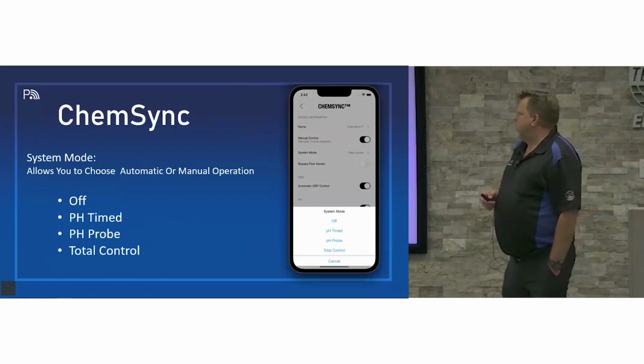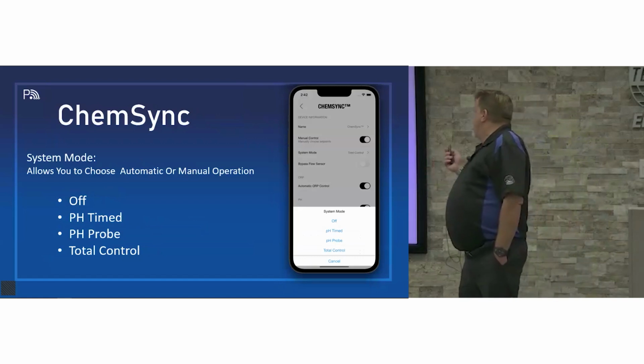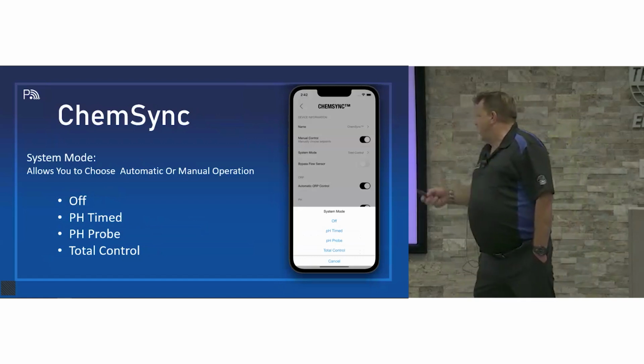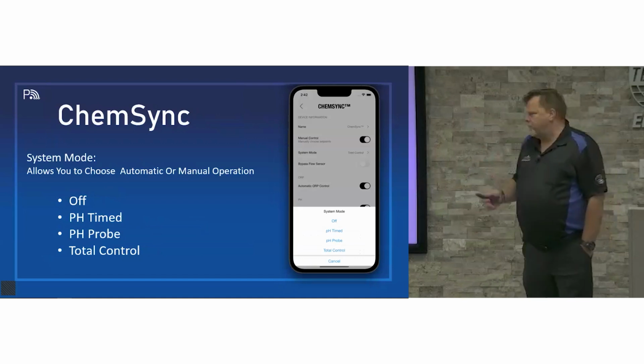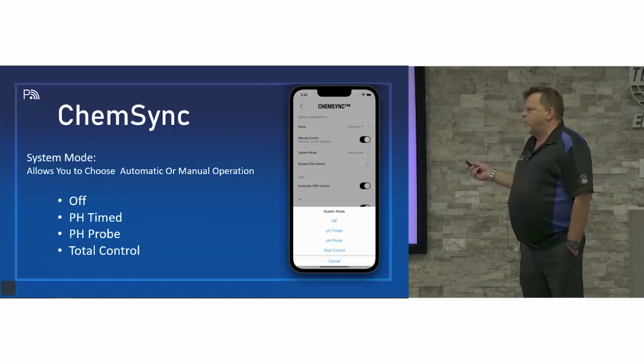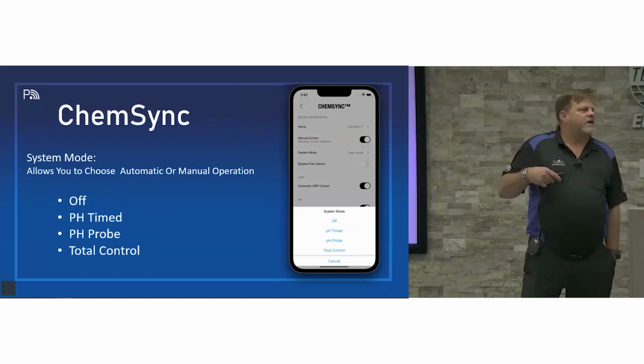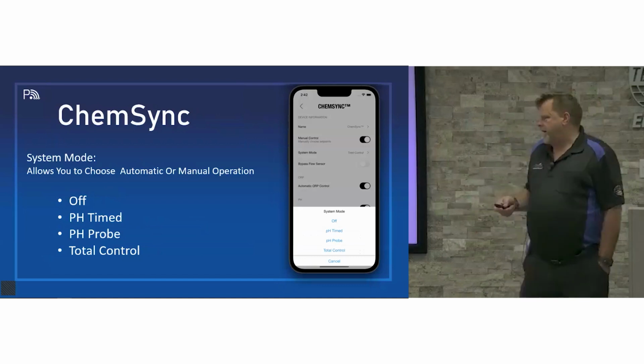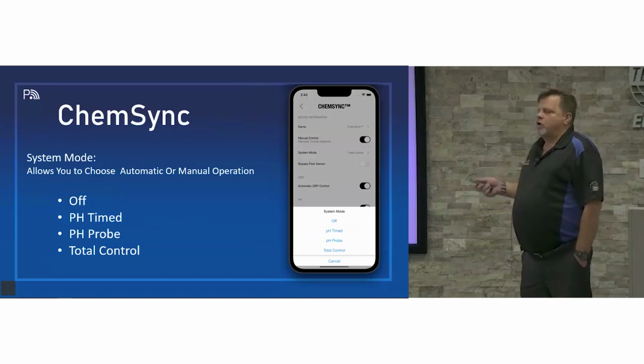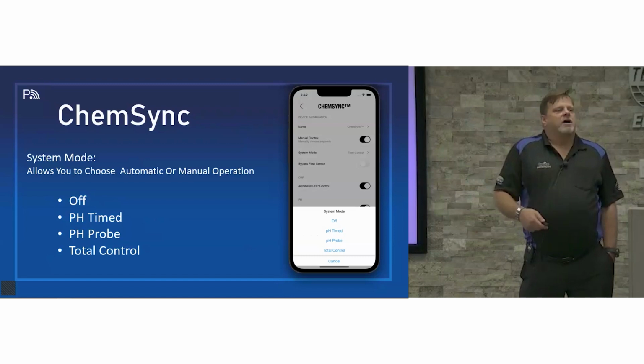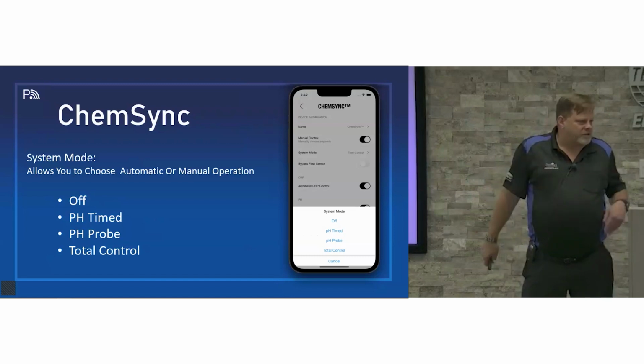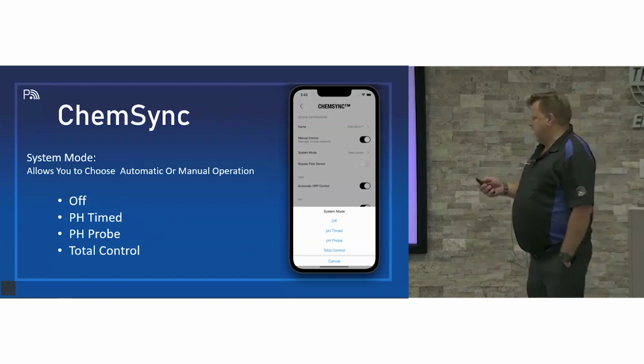In the ChemSync mode, you have the capability of clicking on system mode, and you can turn it off. You can put it in pH timed mode, where you feed acid via a time schedule. In that mode, you won't be monitoring pH. You'll just be feeding an amount of acid that you program for a certain amount of time.